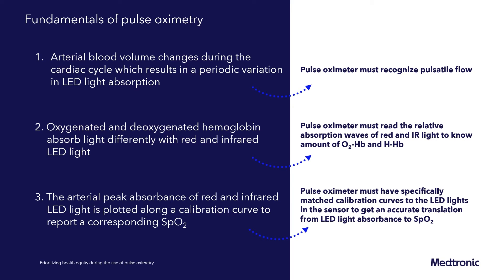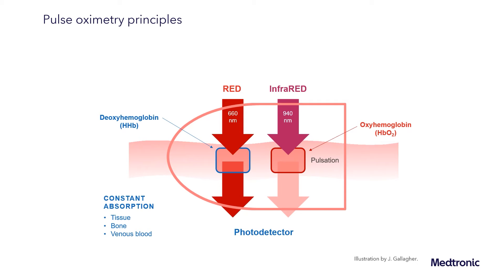This diagram illustrates the basic function of a transmittance pulse oximeter sensor with two wavelengths of light, red and infrared, passing through the tissue bed to be detected by the photodetector on the other side. Through the sensor is the pulsation of arterial blood, which expands and contracts with each pulsation, allowing the sensor to detect the change in light absorption and calculating the plethysmography or pulse waveform.